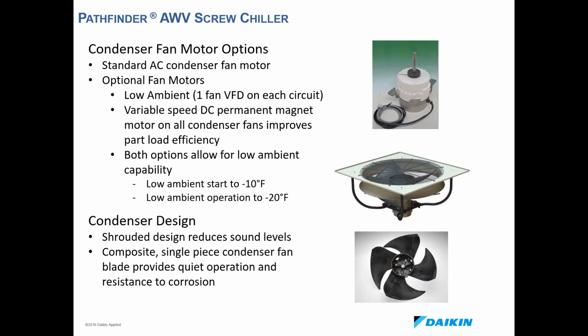Whereas in the DC scenario, all the fans are going to be tied to an EC module, which will vary the speeds of the fans individually. So it gives you a lot tighter control. Both options will allow for low ambient capability. You can run down to -20 Fahrenheit on AWV and start up down to -10. So if the temperature were to go lower than -10, you wouldn't be able to turn the chiller off and start it up again until the temperature rose back up above -10.